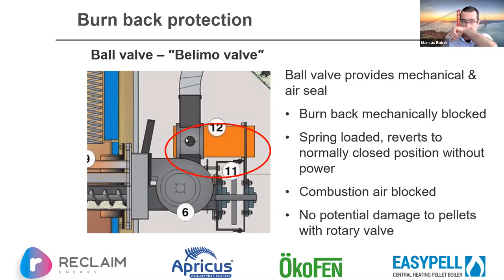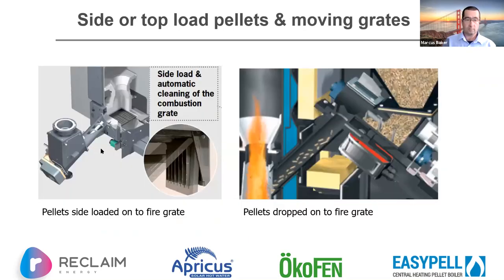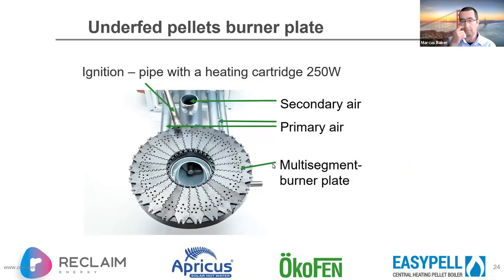In the Ökofen context the ball valve has a double gasket, making it also a gas seal — the only way air can enter the combustion chamber is through the fan system, so it's entirely controlled. Pellets can be fed onto the fire grate from the side, dropped from the top, or — in the Ökofen context — fed up from below, just as an old underfed-grate coal boiler works.